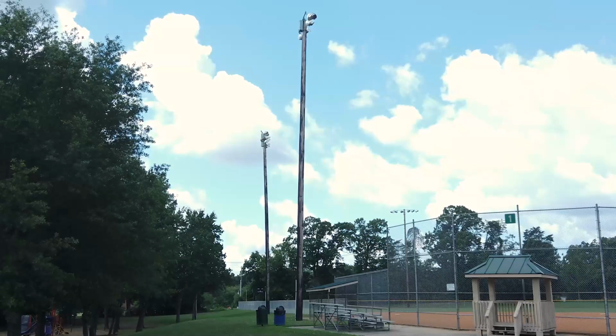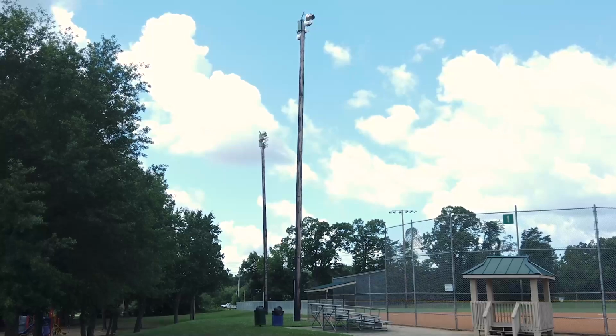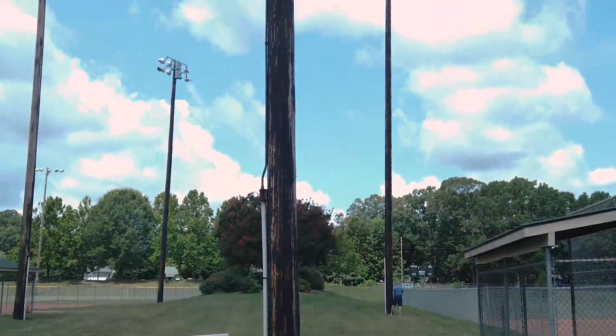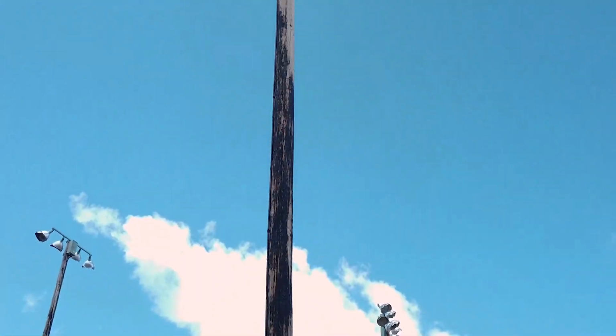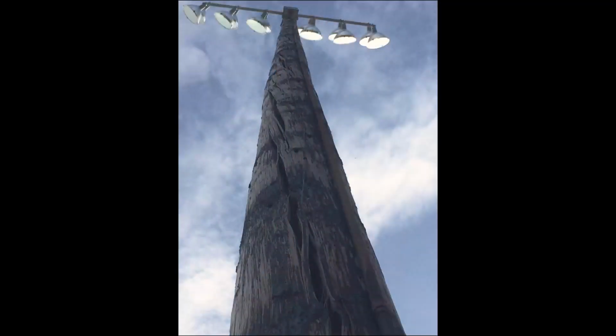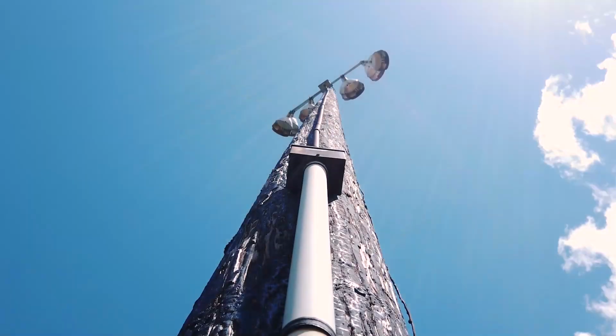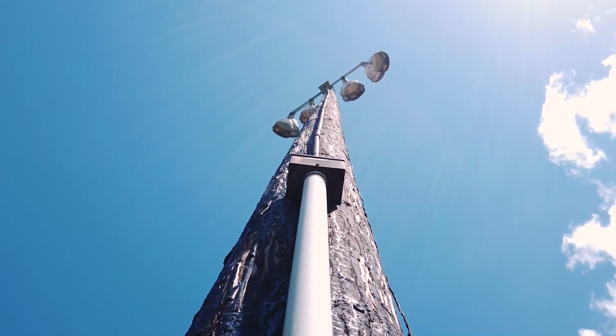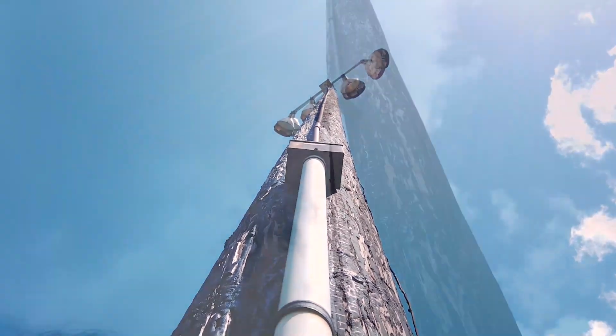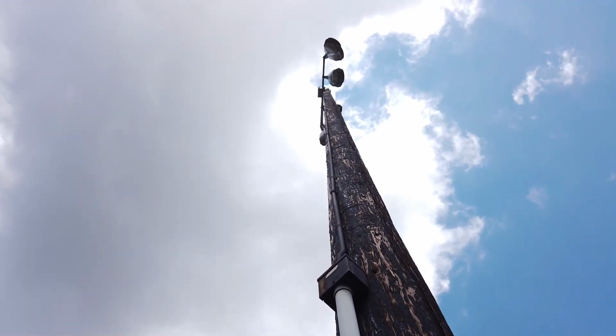If your facility has wood poles, it's important to look for any signs of leaning, cracking, or twisting, which is fairly common for wood poles as they age. Twisting of poles, which is evident by seeing large spiraling vertical cracks, reduces the core strength of the pole. When leaning or twisting occurs, it affects the alignment of the luminaires and can reduce the light levels being achieved on the field of play.